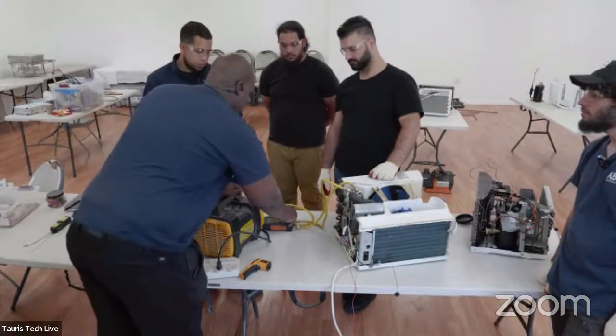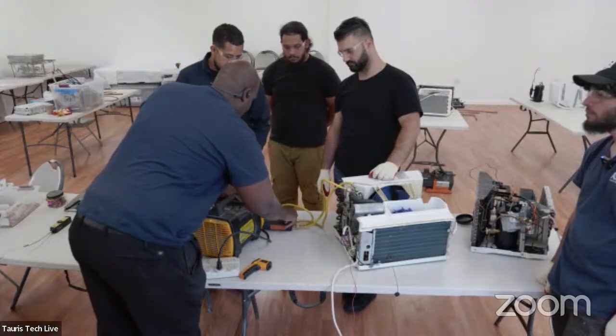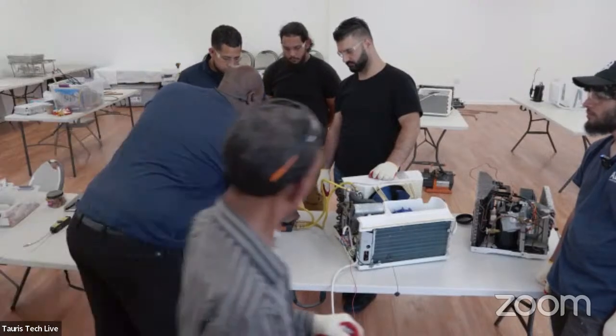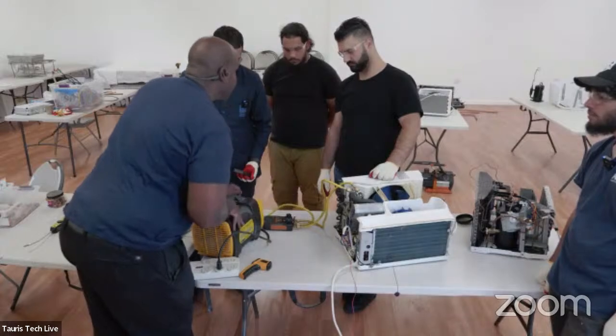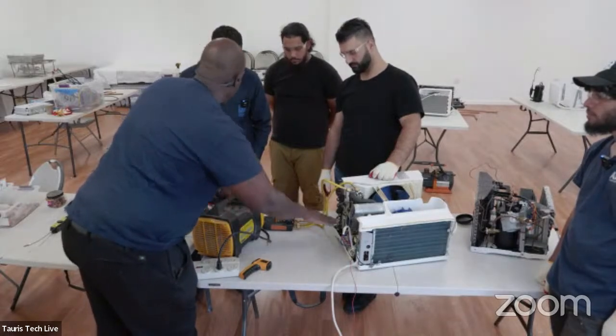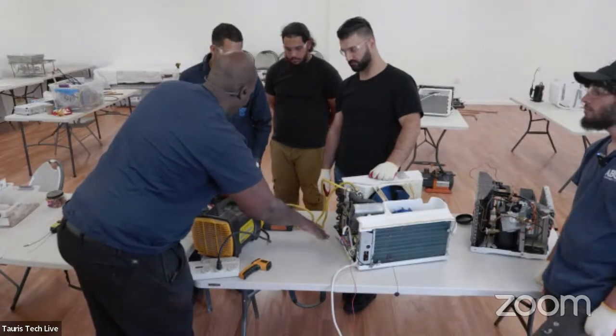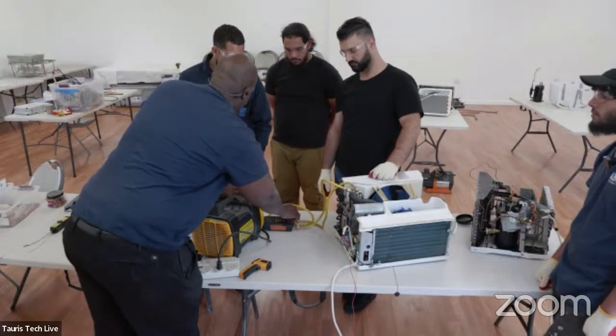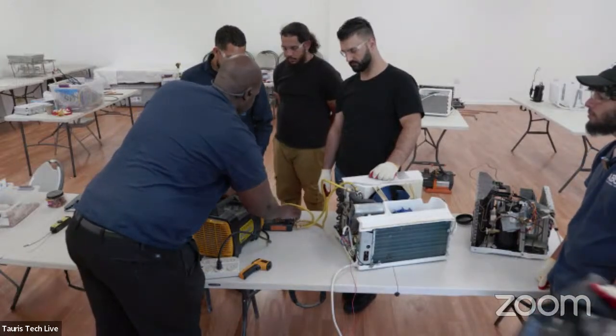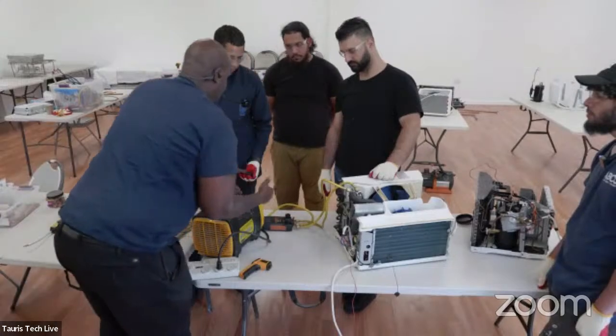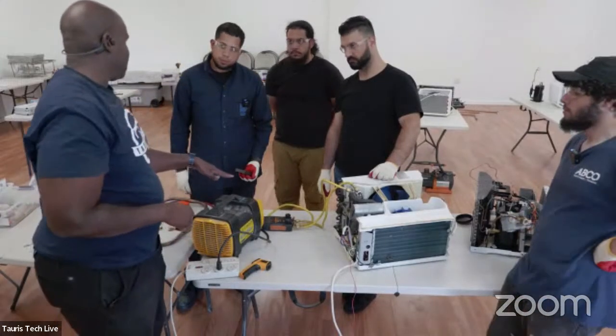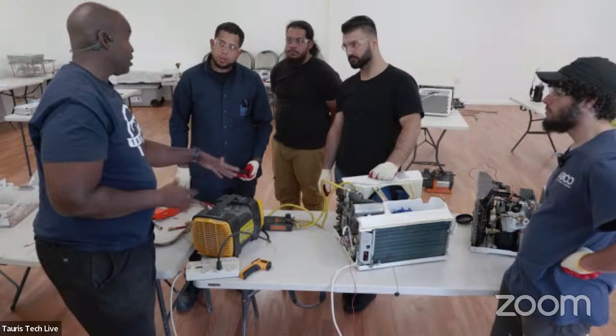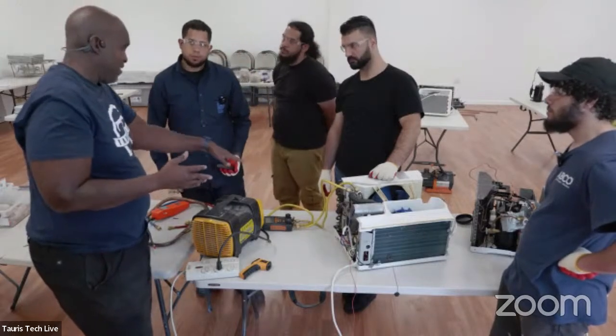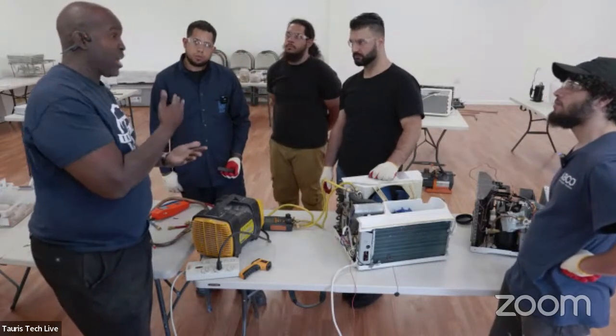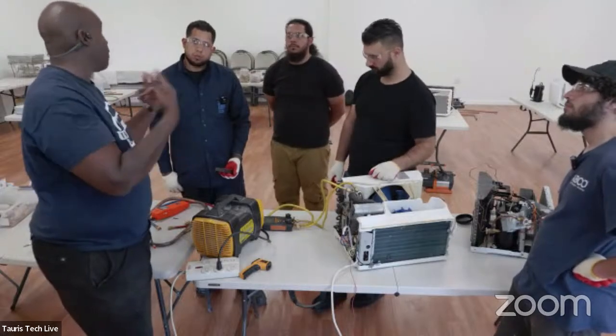If I close this, it will go right back up, because there is still refrigerant in the oil. So I'm running it as long as I can. Now, if I can get it down to 10 inches and it stays at 10 inches, I'm okay. But if it doesn't, there's still refrigerant in the oil — I have to boil that refrigerant out.